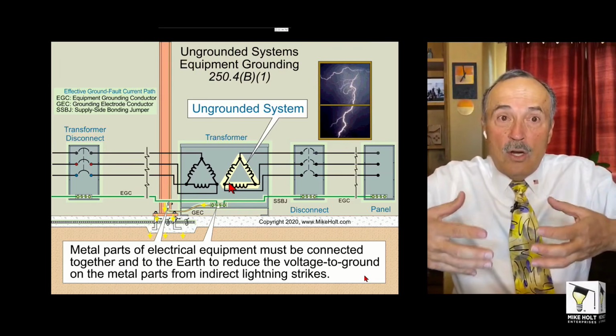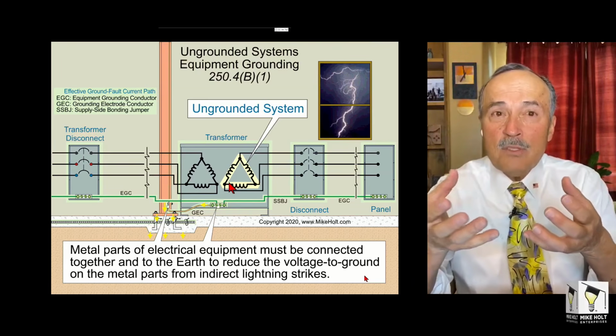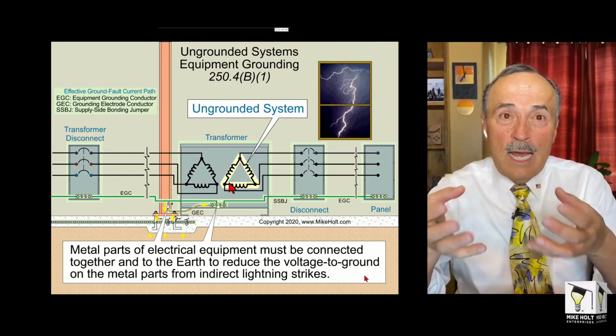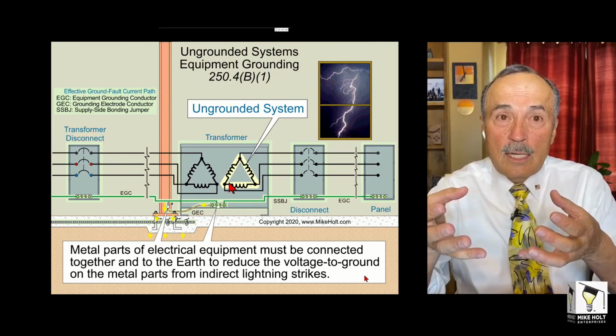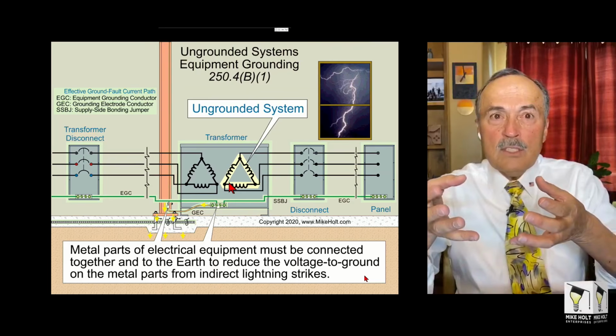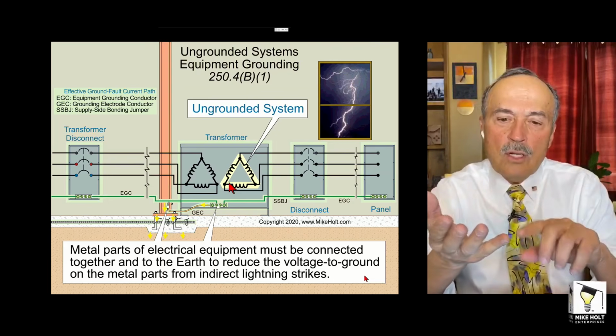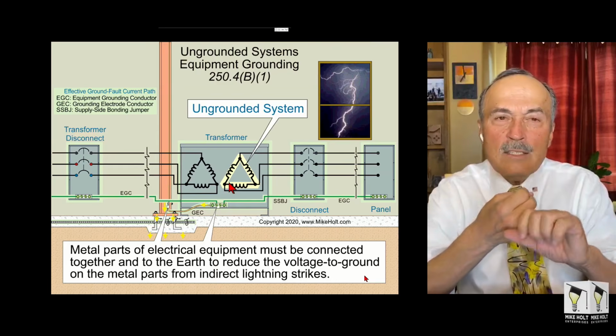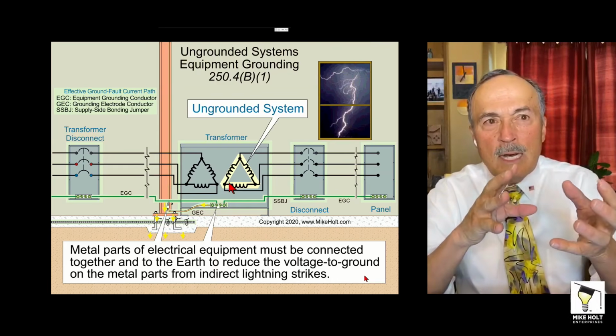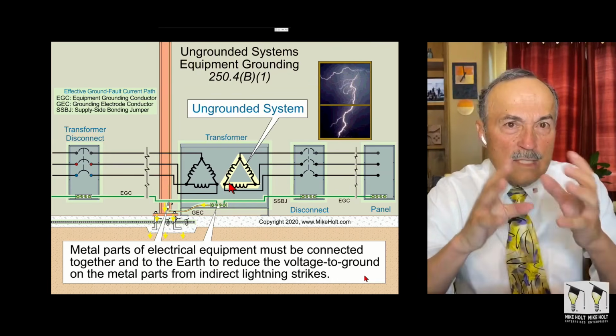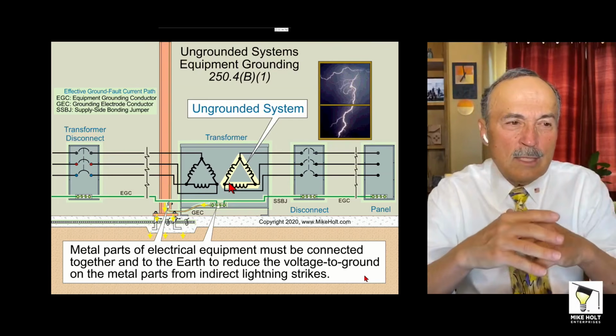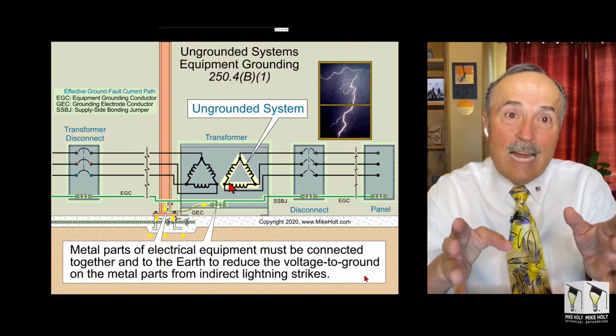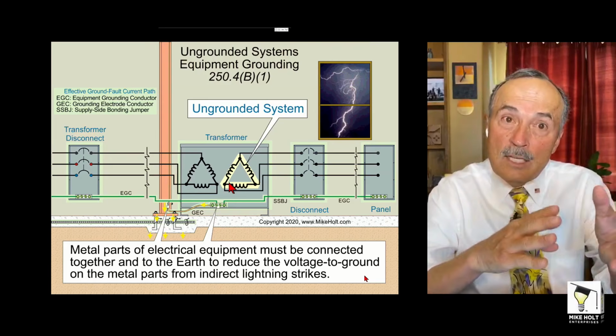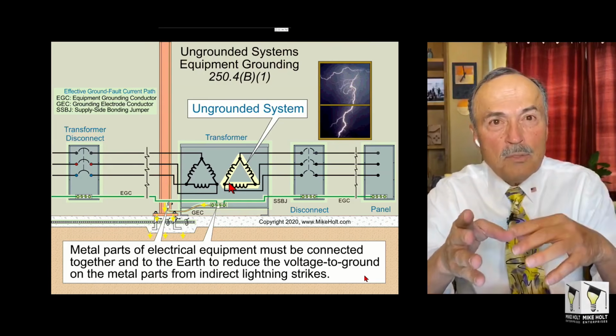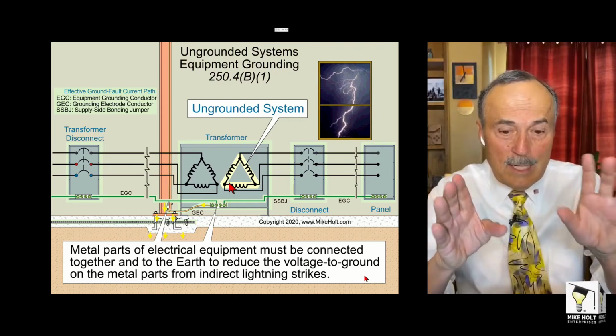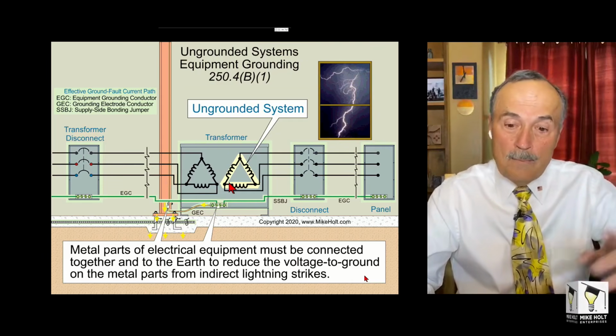And they keep getting a charge until it gets to about 6 or 8 times the rating of the actual line to ground voltage, or rather line to line voltage, whatever it is, and then all of a sudden it discharges. Well, when it discharges in motor windings and in relays and things that don't have the same insulation properties as conductors, it damages equipment. So ungrounded systems, I won't say they're unstable, but they're not desirable. Unless there are applications and places like, I think, in ships and other locations, but I don't know enough about that. Somebody decided that's what they want, okay.